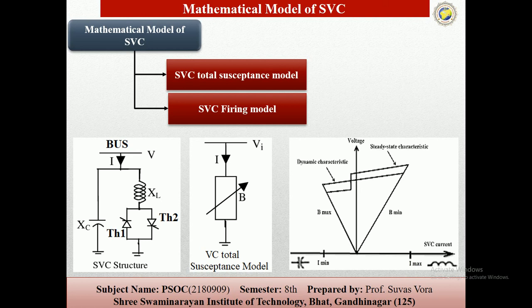You can see the last figure of the steady state and the dynamic voltage control characteristic of the SVC. Within the control range, the current, susceptance and reactive power change according to the control voltage following the slope characteristic. This one is called the slope characteristic. The slope value depends on the voltage regulator and the desired sharing of the reactive power produced between the various sources of the system.